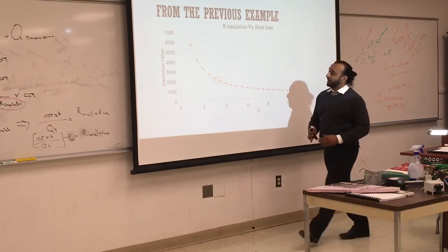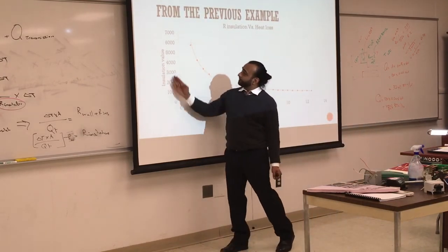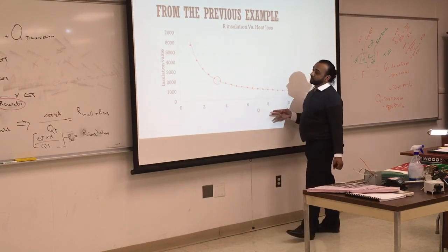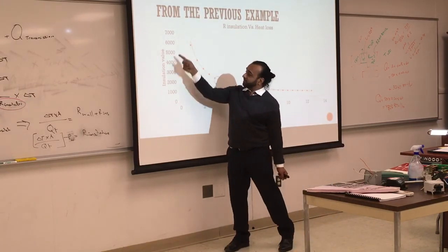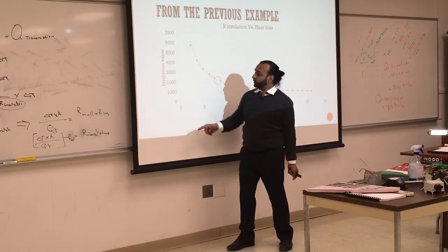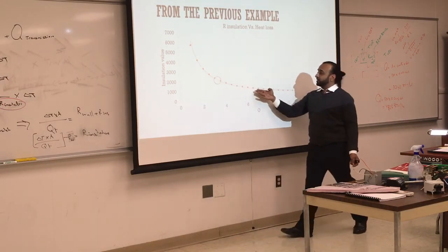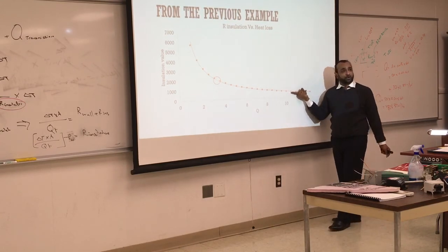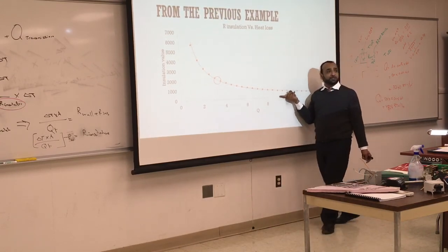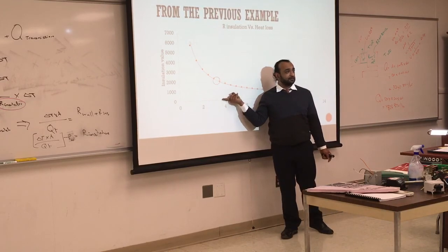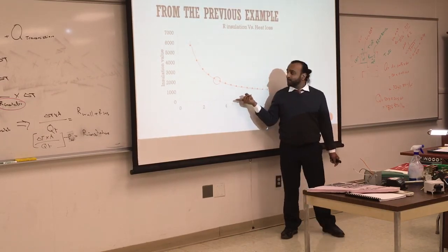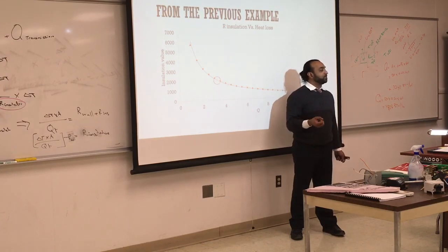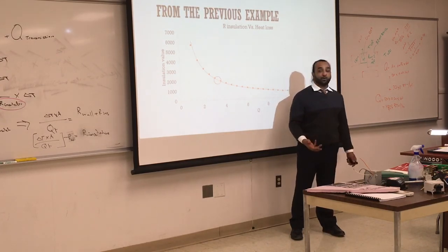And if you apply that, I'm plotting now the heat loss versus the insulation. Actually, this is flipped. This is the heat loss, this is the insulation. You look at the graph here, and you see at some point there is some reduction, but it's so insignificant. It looks like it's going to be stagnant. So you don't have to do any of that, but it's good to know that at some point you can keep adding insulation, but it's not going to add.